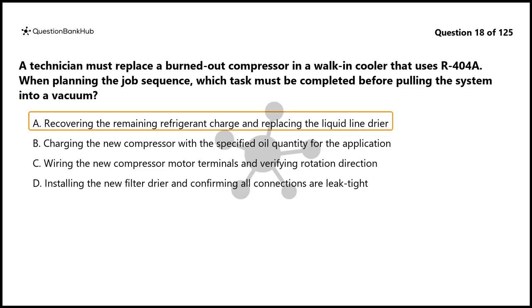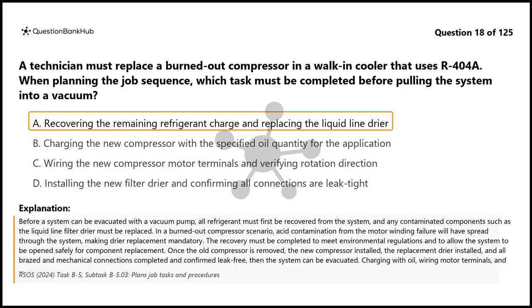The correct answer is A. Before a system can be evacuated with a vacuum pump, all refrigerant must first be recovered from the system, and any contaminated components such as the liquid line filter dryer must be replaced. In a burned-out compressor scenario, acid contamination from the motor winding failure will have spread through the system, making dryer replacement mandatory.